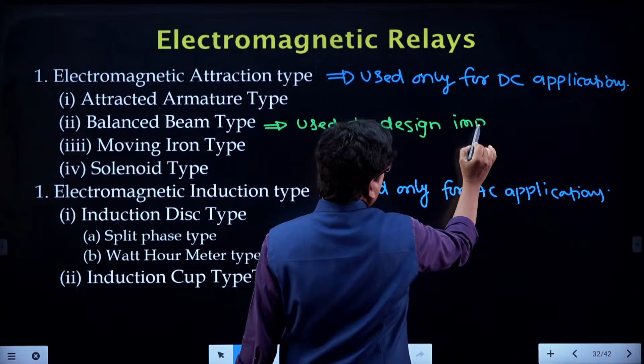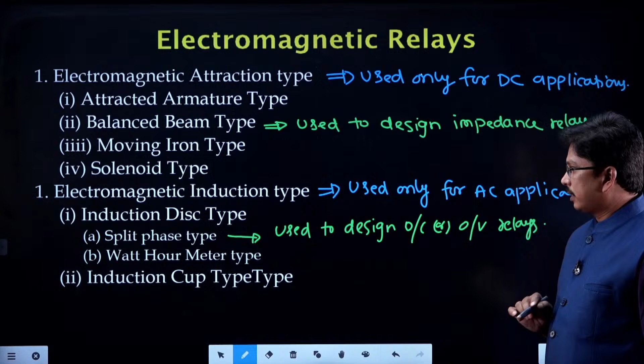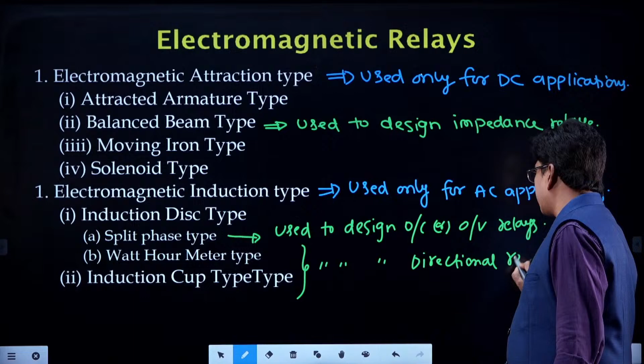In the induction disc type, we have the split phase type and the watt-hour meter type. One point you can expect here is that the balanced beam type is used to design impedance relays. In distance relays, the three types are impedance relay, reactance relay and Mho relay, and the impedance relay can be designed by the balanced beam structure. The split phase type is used to design over current or over voltage relays. The watt-hour meter type and the induction cup type are both used to design directional relays. Right, students? These are the applications of the various constructions.